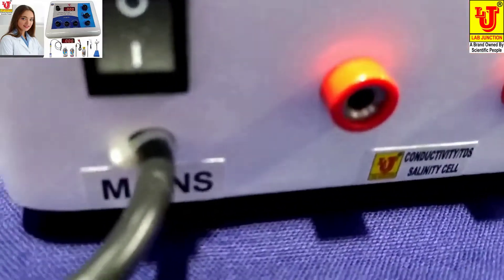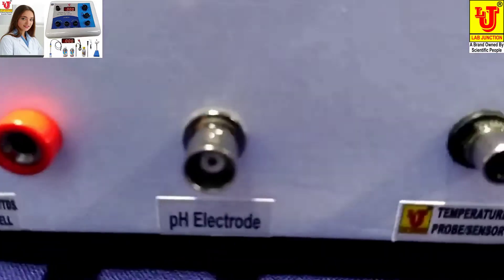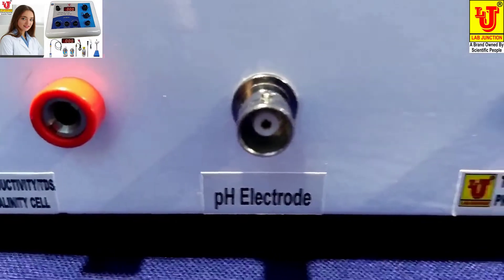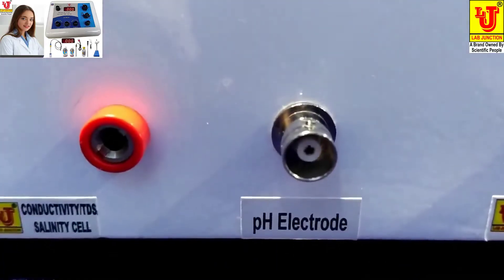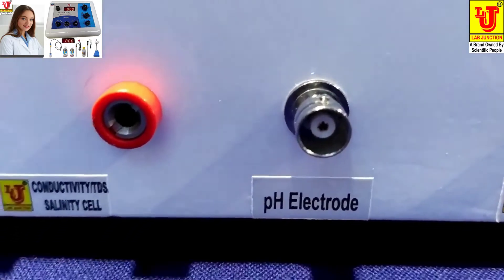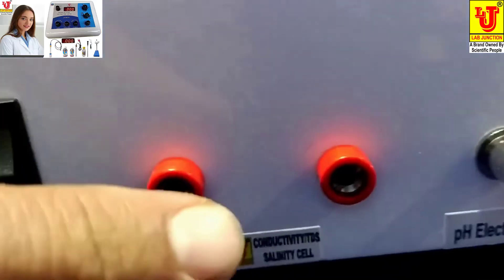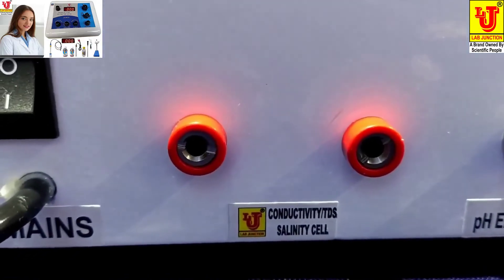Now this is the side control and back control. In the back control, first is the temperature sensor connector for inserting the temperature sensor. Next is pH BNC connector for inserting the pH electrode. Third one is for connecting the conductivity TDS cell sensor.